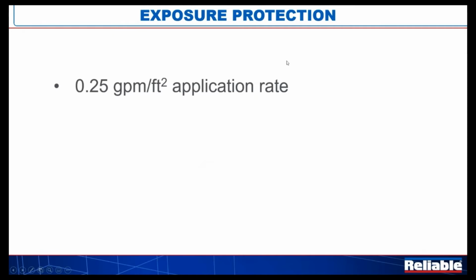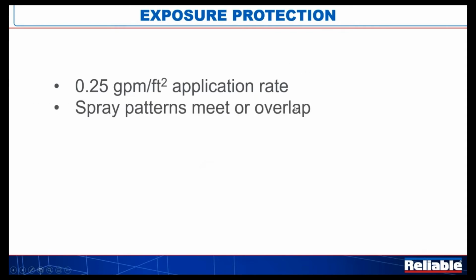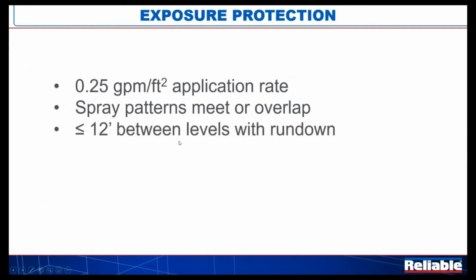Exposure protection. So again, envision the propane tanks, LNG tanks, whatever they are, sitting out in the middle of a field there. 0.25 GPM per square foot application rate. The spray patterns must meet or overlap. Now, this isn't in all the other sections, but if you think about it, it makes sense, right? You're going to look at the spray pattern. You're going to want to make sure there are no dry spots. But in this case of the exposure protection, it is very clearly stated that the spray patterns must meet or overlap.